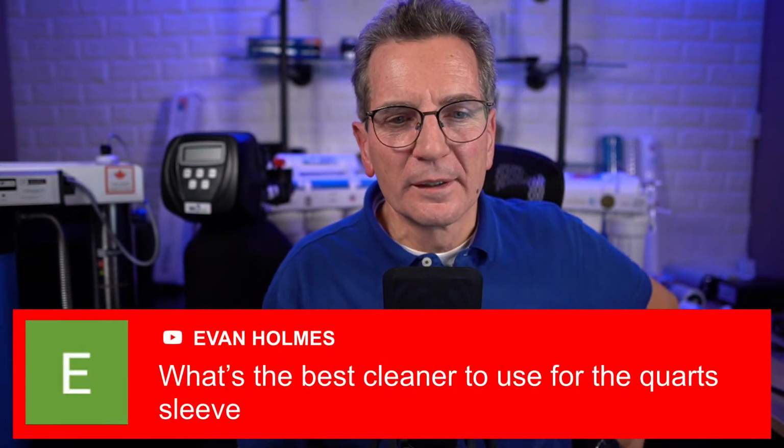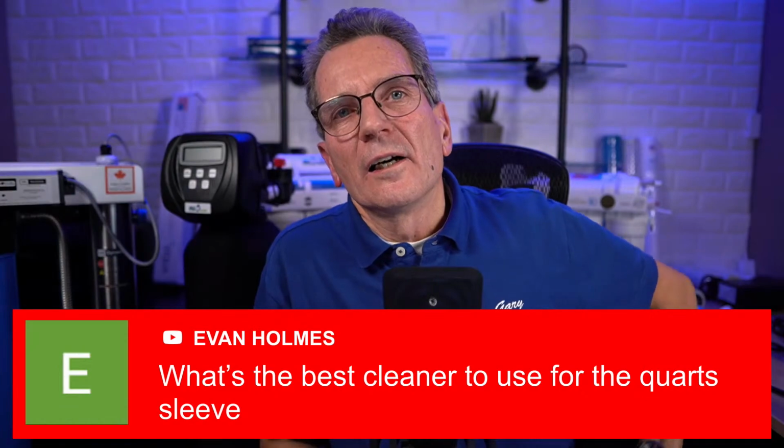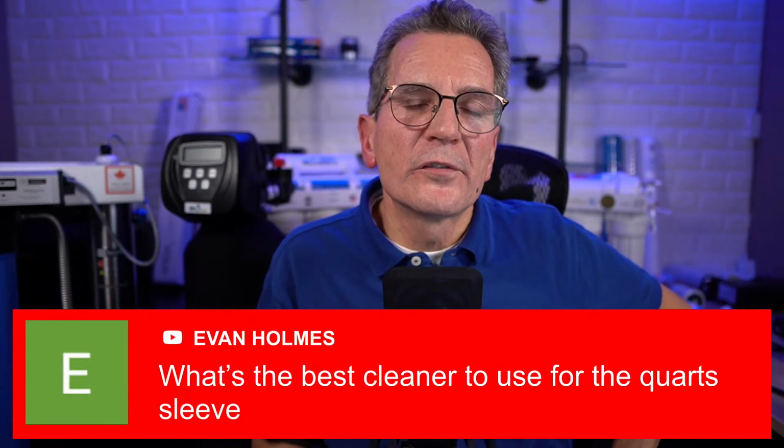And here's a great question from Evan. What's the best cleaner to use for the quartz sleeve? I use CLR. I mean, folks say you can use vinegar, you can use other cleaners and that kind of thing. I use CLR. I find that it works well, it works quickly. If I'm doing a service call in your home, you don't want me hanging around for 45 minutes waiting for the vinegar to start to clean up that sleeve. But remember, that sleeve has to be clean. If you can't get that sleeve clean, you have to replace it.